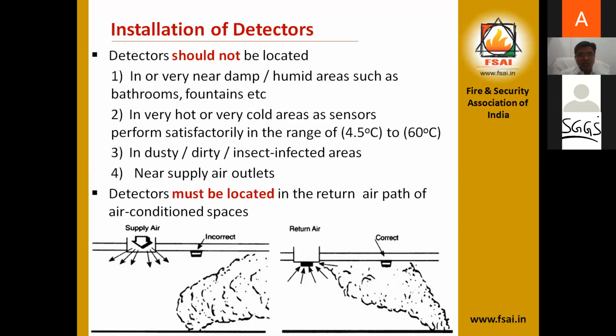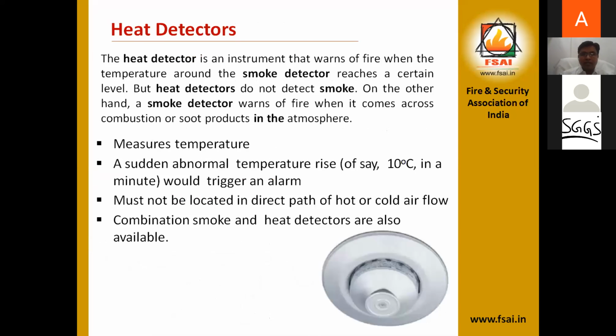We have to always install the detector in the return air path so that it will work perfectly and be useful for fire evacuation. Next is the heat detector. The heat detector is an instrument that warns of fire when the temperature around it reaches a certain level. So when the temperature increases, the heat detector starts giving a signal. But heat detectors do not detect smoke. For that, we have to provide smoke detectors.